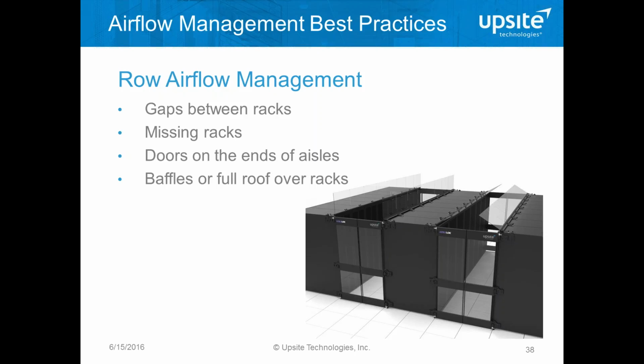So these openings need to be sealed so that the only way that air leaves the cold aisle is passing through the IT equipment. One of the areas that we see the most hotspots is at the ends of rows. And this can easily be solved by putting doors on the ends of the row, either the hot or the cold aisle, depending on which direction you're headed towards containment. And I often tell people that you get a lot of bang for your buck just by putting on doors and not having to go all the way to full containment.